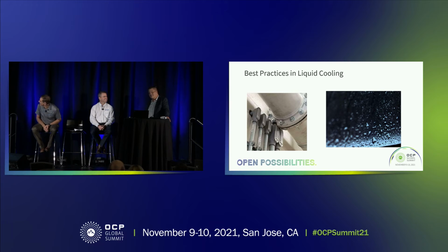So what you're looking at there is a pipe that has condensation on it. Oh, okay. You want to talk about what is condensation and why I put it on this page as being a concern? So condensation is not really a nemesis. It's a well-understood activity inside of data centers. You have dissimilar temperatures of fluids and air. And essentially, it's what happens on the side of your glass when you have ice water in it.